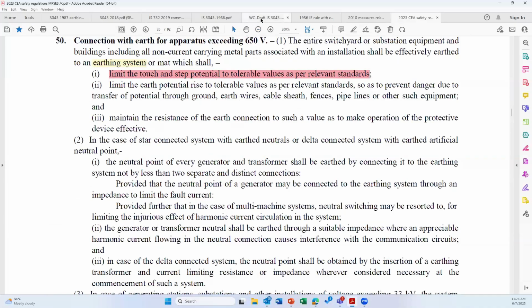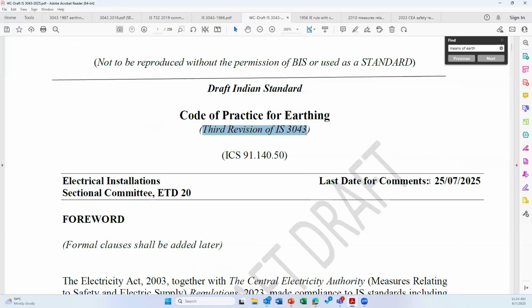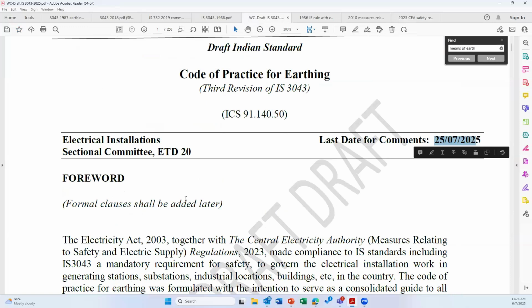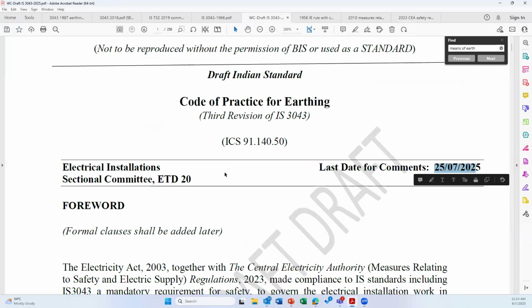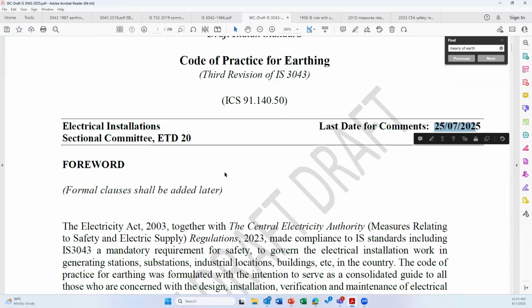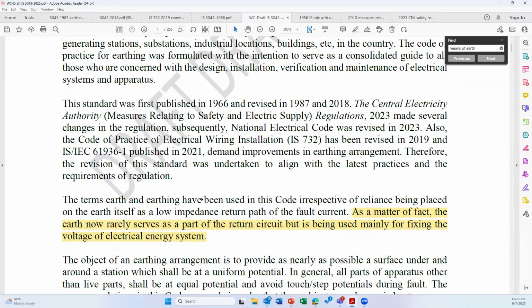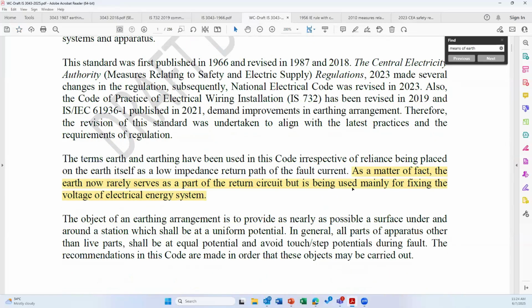So now the new draft IS 3043 was published on 25th of May, and the last date for comments is 25th of July. Starting with the foreword, sometimes people try to read this highlighted portion and interpret it. This portion is from the 2018 IS 3043. As a matter of fact, the Earth now rarely serves as a part of the return circuit, but is being used mainly for fixing the voltage of the electrical energy system. This is the correct way.